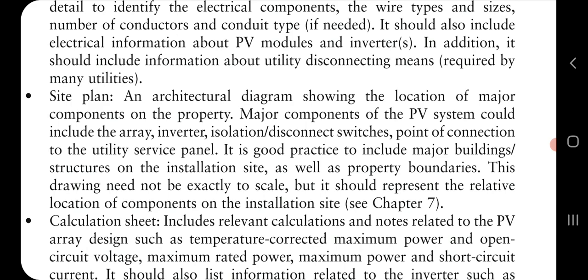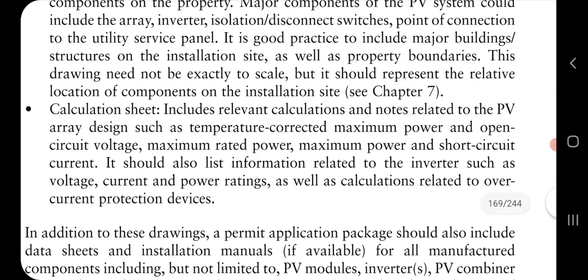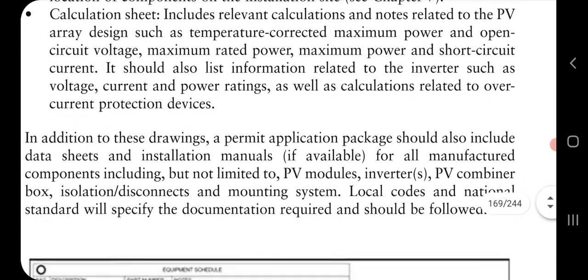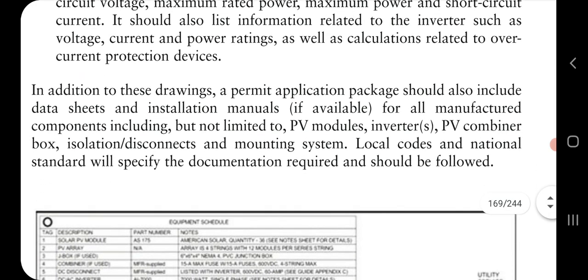And the calculation sheet is also very important, where you can calculate many things like temperature, maximum power, short circuit current, power losses, and open circuit voltage. This is very important, and has to be calculated before the installation. In addition to this, drawings, the permit application package, data sheets and manuals should be taken from the manufacturer.